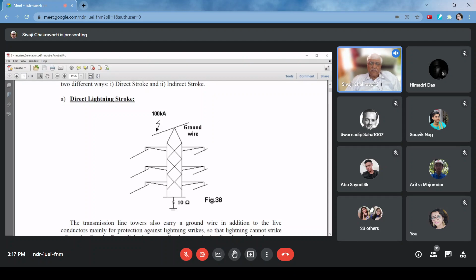This traveling wave travels towards earth, but a traveling wave always has the property of reflection and refraction. So there will be a reflection, and the effective voltage will be the incident voltage plus the reflected voltage. It can be mathematically shown that since the tower footing resistance is 5 to 10 ohm and the tower surge impedance is about 300 to 500 ohms, there will be a negative reflected voltage. So the net lightning voltage is much, much reduced because of this negative reflection. This is one of the reasons we try to keep the tower footing resistance as low as possible. That is part of the tower design.